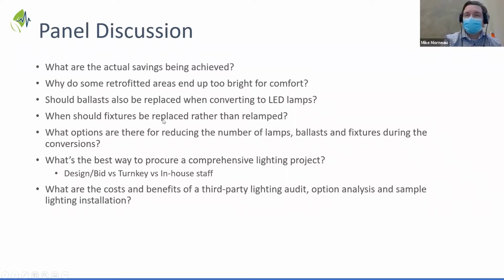Yeah, it's definitely an issue that we see. I think the best solution for the comfort issue around LEDs is to provide more control options to users, to give them dimming functionality and localized control. One issue we see is, for example, in nursing stations that are operating 24/7, a higher light level is required during the day versus an overnight shift. So providing that level of control as part of the lighting retrofit process, and considering that from the inception of the project, is something that can help minimize that overlighting later on.